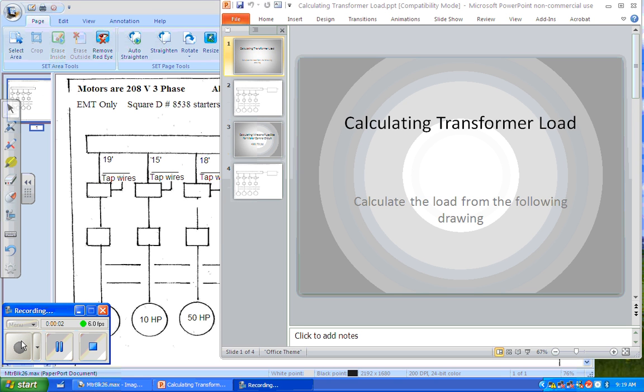All right, we're going to talk about calculating the transformer load. What this gets down to is that sometimes somebody that has a little shop has previously expanded their shop and bought new equipment, and then they want to expand again, and suddenly they want to use a bunch of old equipment that they've had before. And they'll drag it into a room and say, can you hook this stuff up?